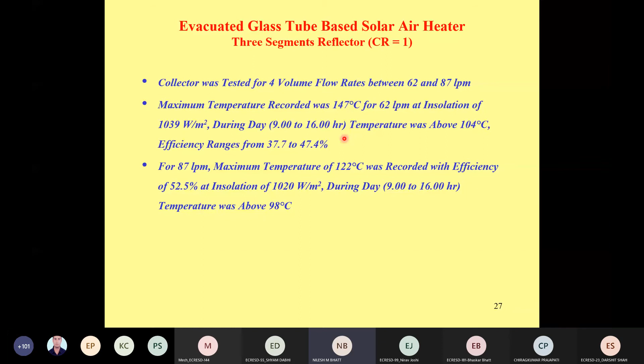Here I would like to mention that this higher efficiency is attributed to a good reflector. In the earlier case, the reflector had low reflectivity. So when you go for a concentrating collector, the reflectivity of the reflector also plays a major role. Suppose your concentration is, let's say, 2. In such a collector, less than 50% of the solar radiation is directly falling on the absorber and more than 50% is falling on the reflector. So if you reduce reflectivity from 0.9 to 0.8, the input to the absorber will reduce significantly. Those who are very comfortable with the subject should immediately raise the query that for the 5 segment, just by increasing the concentration from 1 to 1.6, your performance is very good.